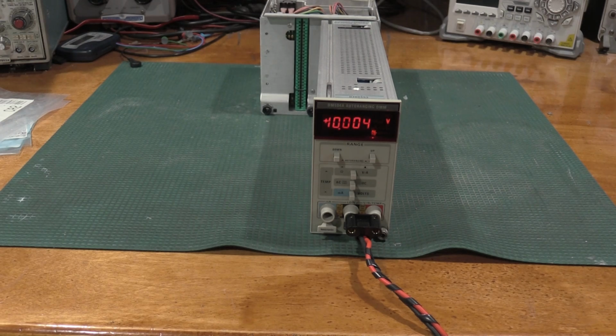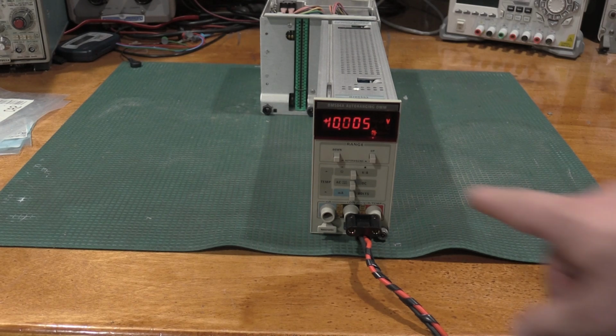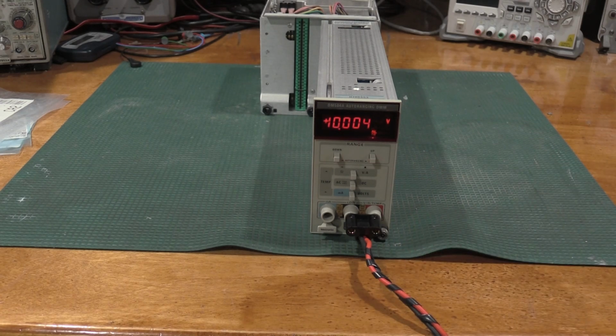Okay, this is one of those where now we have to make a judgment call, and I'm going to talk to the owner after this video posts and see what he would like to do. If he'd like me to reset the calibration constants and go through a calibration procedure, maybe that's what we end up doing. However, I have the appropriate cal gear warmed up, and we're going to run it through some tests here real quick to see what's going on, because at 10 volts, everything looks pretty spot on. I can't ask for more than that on a DMM, and that agrees very much with my 7605. This is within tolerance for the particular meter, and I haven't let this warm up quite yet, so I've got to let this warm up and go from there.